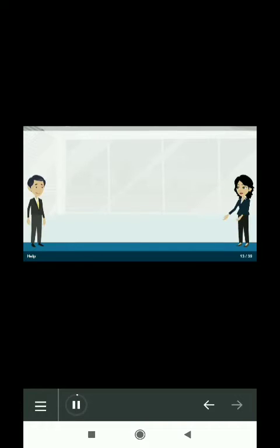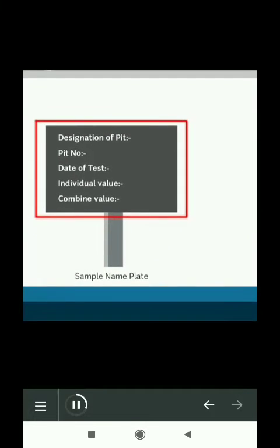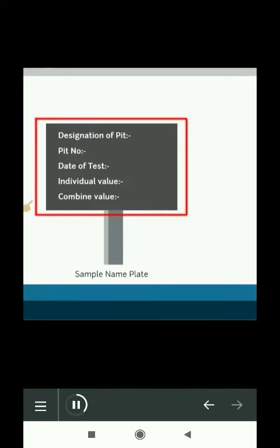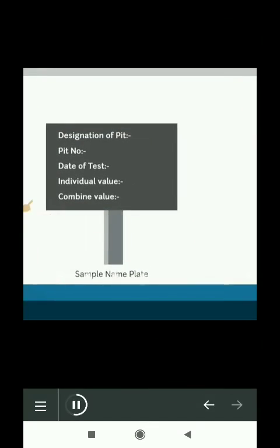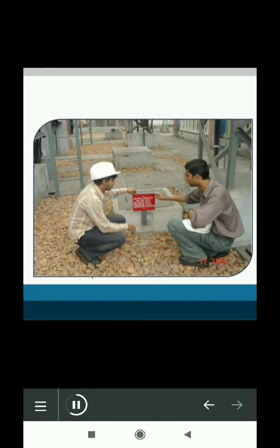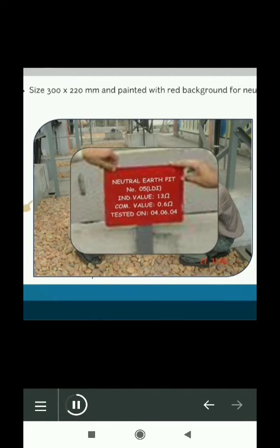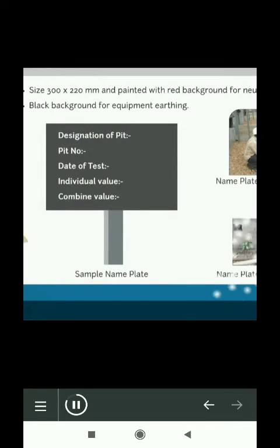So Mayank, we have seen the different dimensions for different pits, but how do we differentiate the pits? Is there any way to do that? Sure, there is. Previously, we have seen the dimensions of earthing pits required when they are constructed. So after construction, earthing pits are provided with identification plates. It looks like this, and these are the required fields. These identification plates have the following dimensions. For neutral earthing, the size should be 300 by 220 mm and painted with red background for neutral earthing station and black background for equipment earthing.